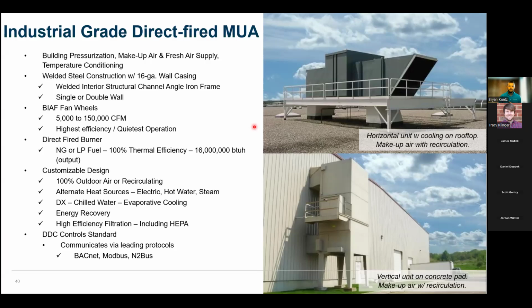But really, the other big piece is the customized design. From trying to match footprints to the unique controlling that Jamie was talking about within this facility, it's really kind of a Lego set of whatever you need an air handler to do for your facility. We also offer cooling upwards to 65,000 CFM. That's about the cap for that. And then we can also offer electric, hot water, steam as alternate heat sources. We offer energy recovery, and we also offer filtration upwards to the HEPA filters. DDC controls are standard. We do have some other offerings from a control standpoint as well that I'll touch on more here in a few slides.